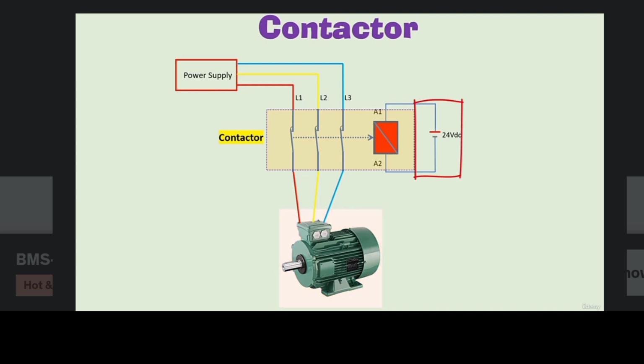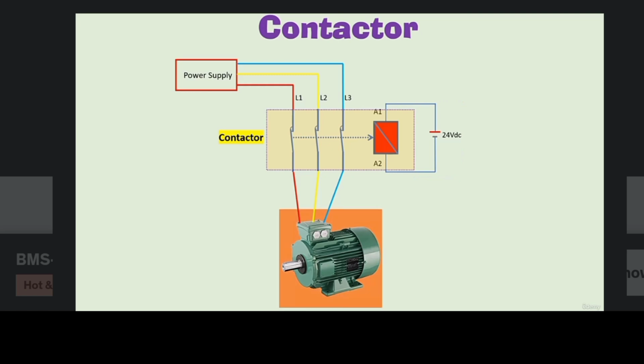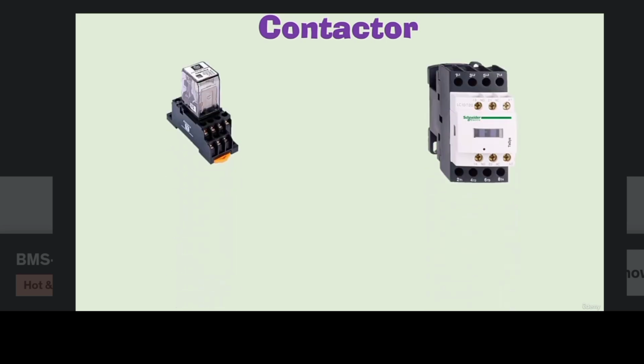This control voltage to energize the contactor is supplied by a DDC controller, or it could be supplied by a selector switch inside the MCC panel. As we saw, the working principle of both relays and contactors is the same, but they have different applications. Relays are used for switching of low current applications like dampers and valve actuators. Contactors are used for high current load applications like fan motors, elevator motors, and pump motors.